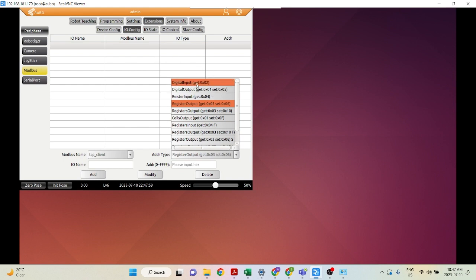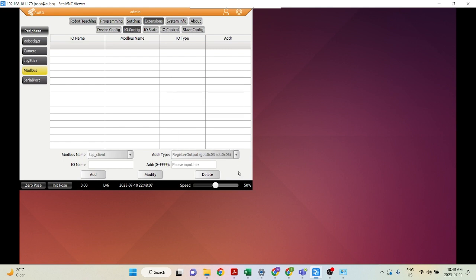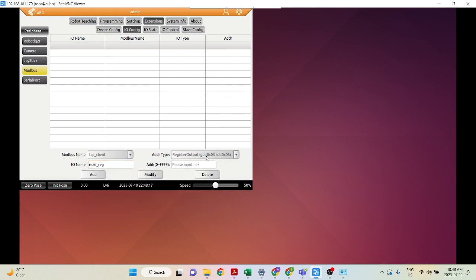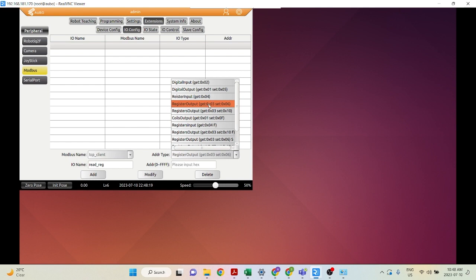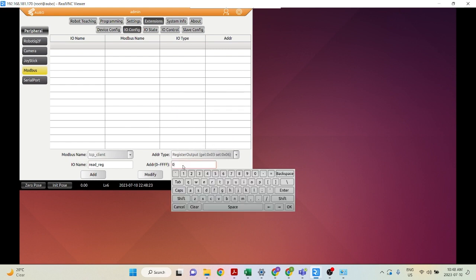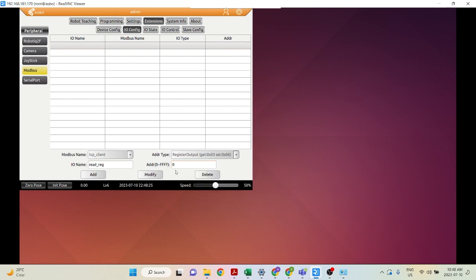Digital input is read-only, however digital output is read and write. Register input is read-only and register output is read and write. Let's create one right now — I'll create one called 'read register' and select register output, with address set to 0. We'll see where this number is used later on. Click Add.